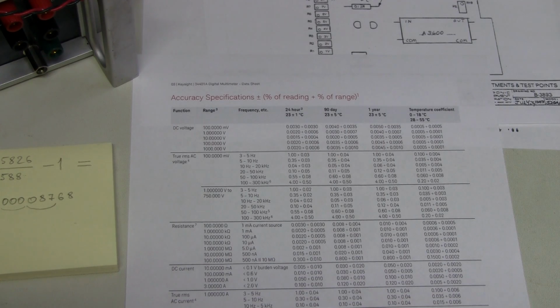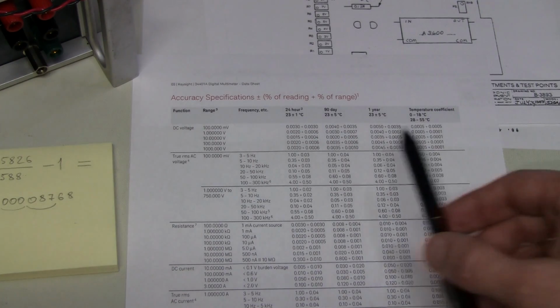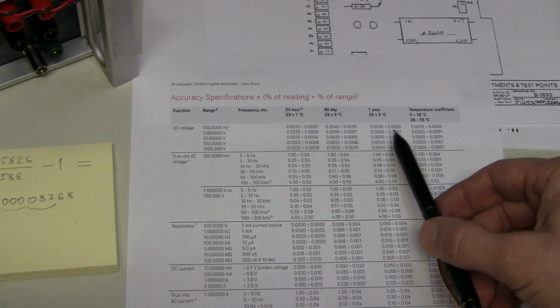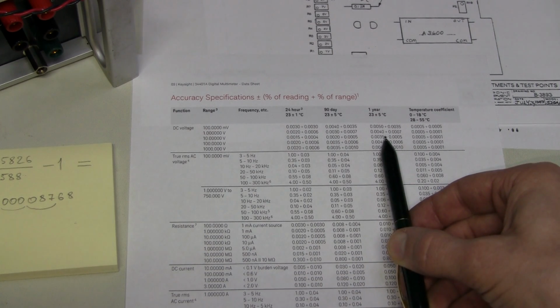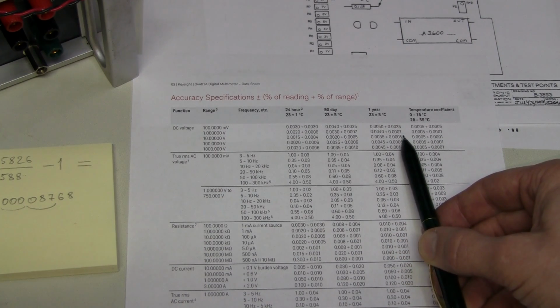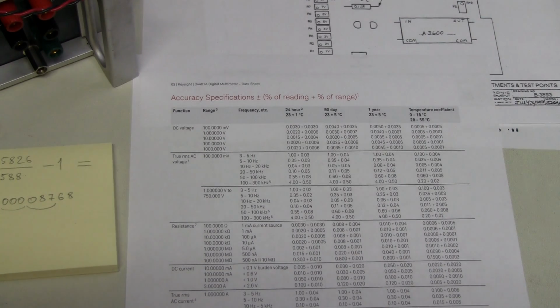Let's look at the specs of my meter. If you watched my recent videos, in one of them I repaired another voltage calibrator, which was Fluke 341A, and in that video I compared my meter side by side with a new model 34461A, which had a certificate of calibration within 1 year, about 1 year, by Keysight. So let's assume my meter is in calibration, because the meters agreed almost perfectly within a few microvolts. So on this range, 10 volt range, we have 1 year 35 ppm of reading plus 5 ppm of range at 23 degrees C, plus minus 5 degrees. So roughly speaking, it is about 40 ppm.